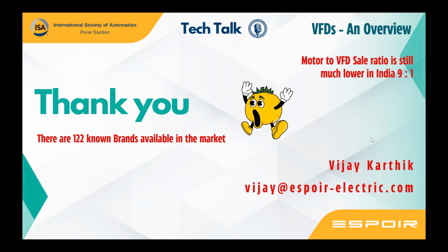Then some questions. The question by Mr. Sanjay Mishra is on the VFD for HVAC application. Primarily the HVAC industry is a parallel industry, and general industrial VFDs are not used. Primarily on one aspect, they ask for something called fire retardant. The components of the VFD should be certified and comply to that standard. Then a communication protocol with the BMS, like Apogee, LONworks, all that feature is required, which a general industrial drive doesn't have. The most important factor is something called emergency operation of a pump.